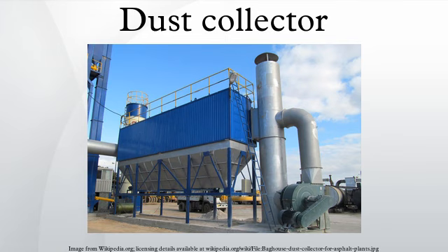Characteristics of airstream. The characteristics of the airstream can have a significant impact on collector selection. For example, cotton fabric filters cannot be used where air temperatures exceed 180 degrees Fahrenheit. Also, condensation of steam or water vapor can blind bags. Various chemicals can attack fabric or metal and cause corrosion in wet scrubbers.